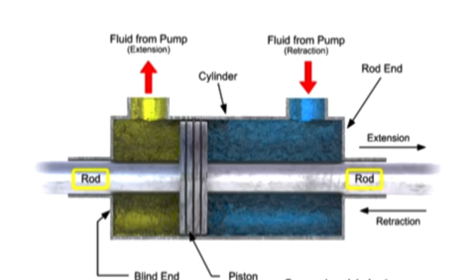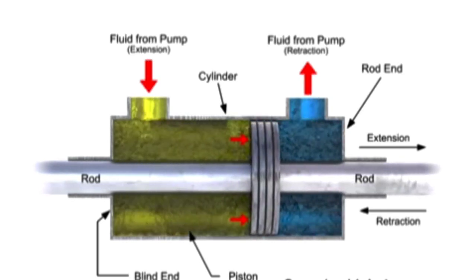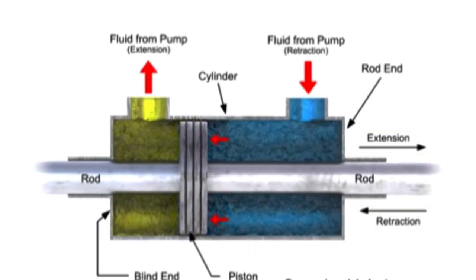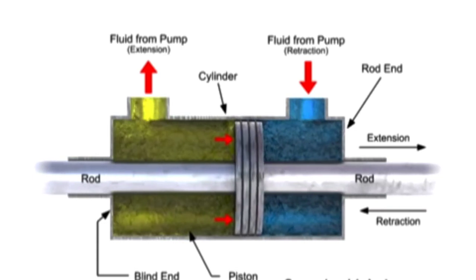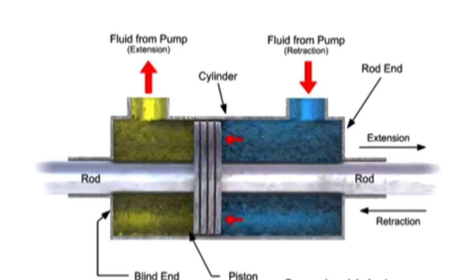They have two rods, both attached to the piston, and each coming through an end cap. Double-ended cylinders work similarly to single-ended, but are used when a constant speed is required for both the extension and retraction strokes. Since the flow rate is the same and the piston areas are the same, the speed for extension and retraction is also the same.